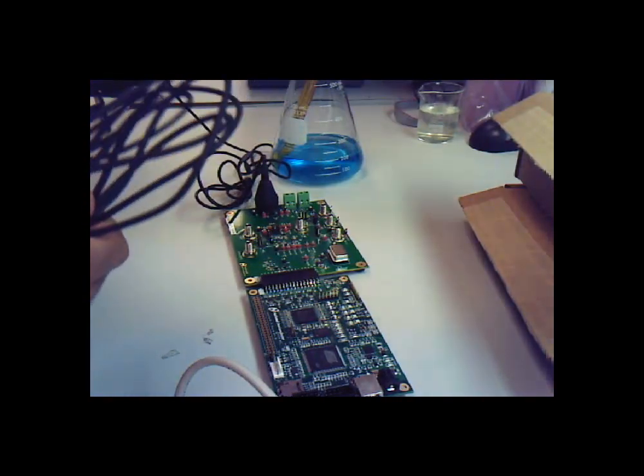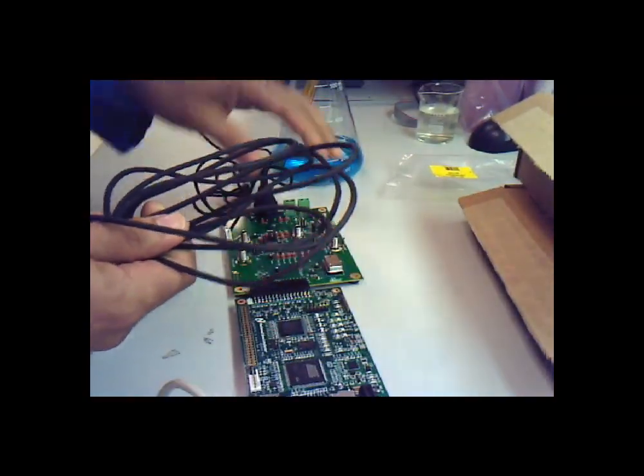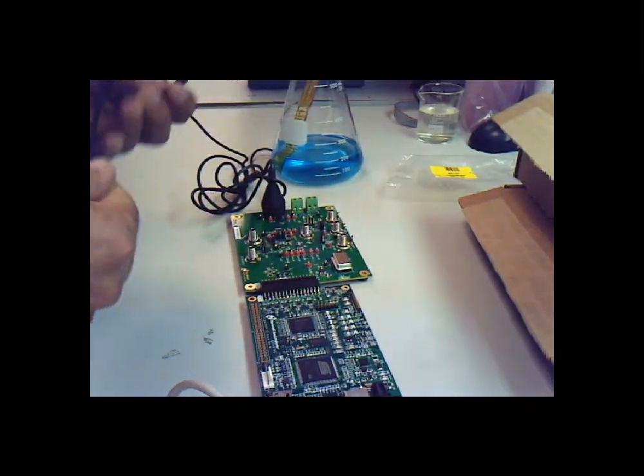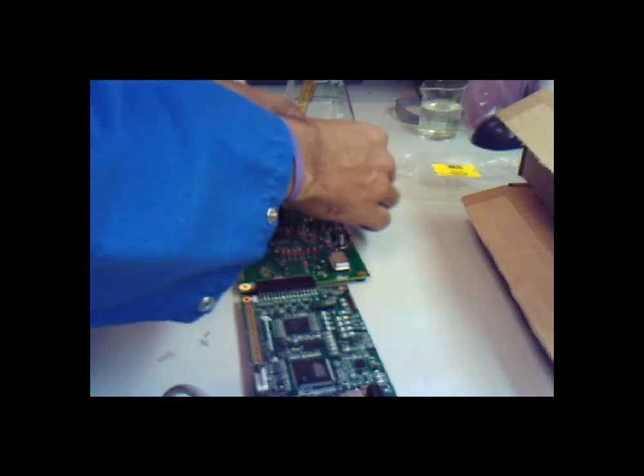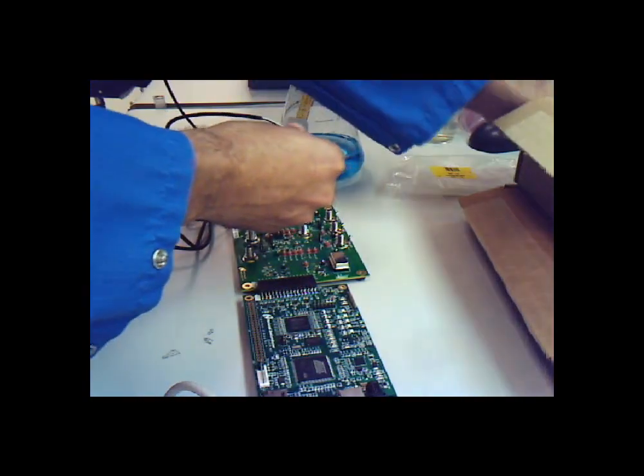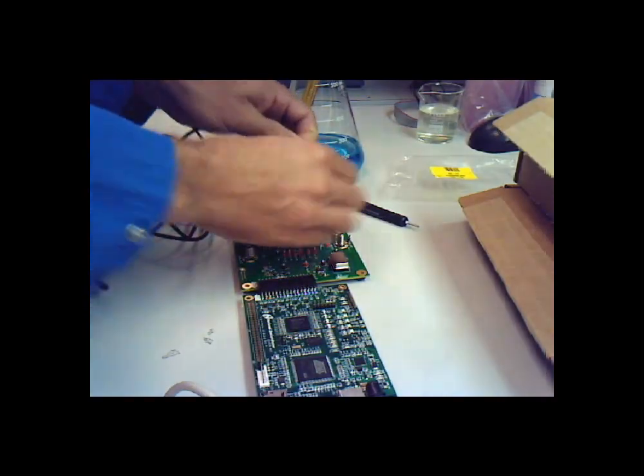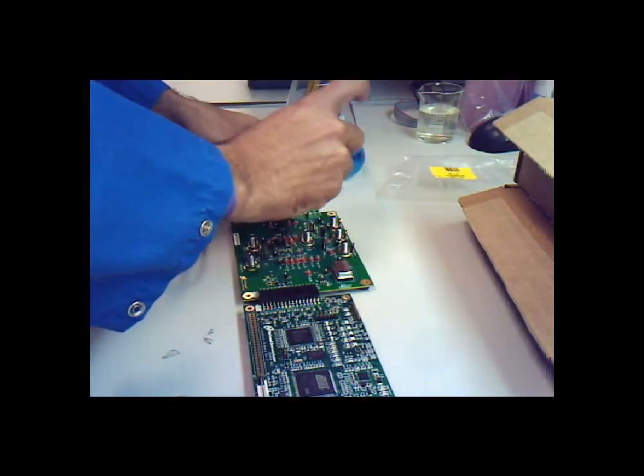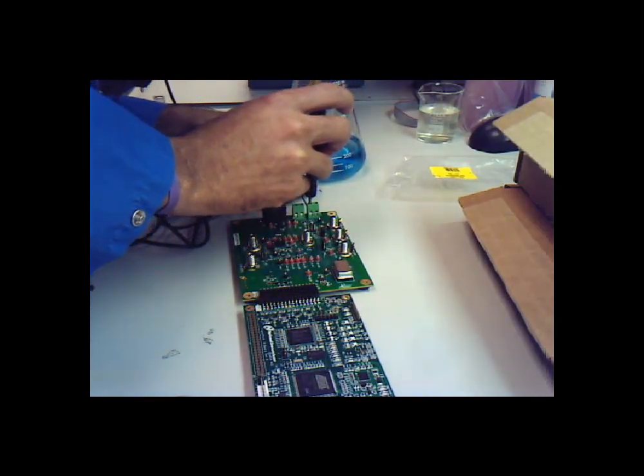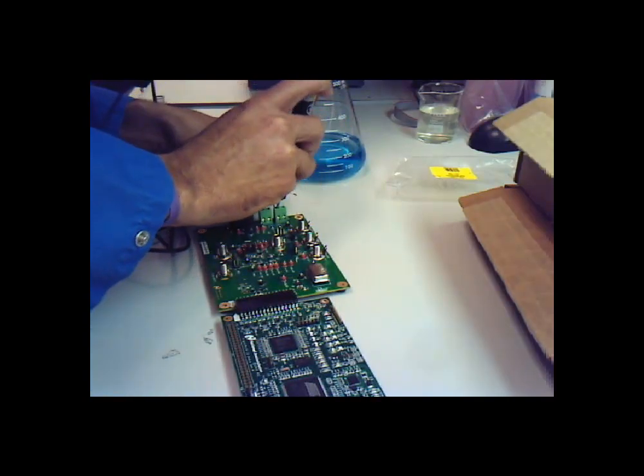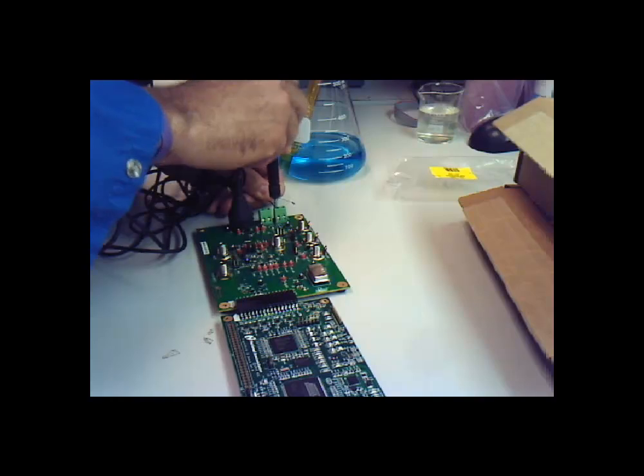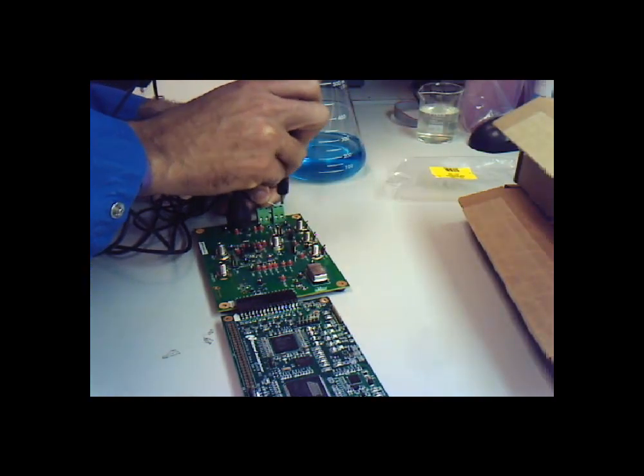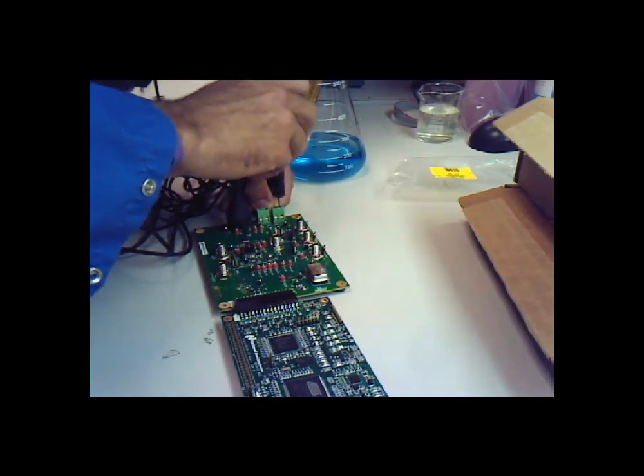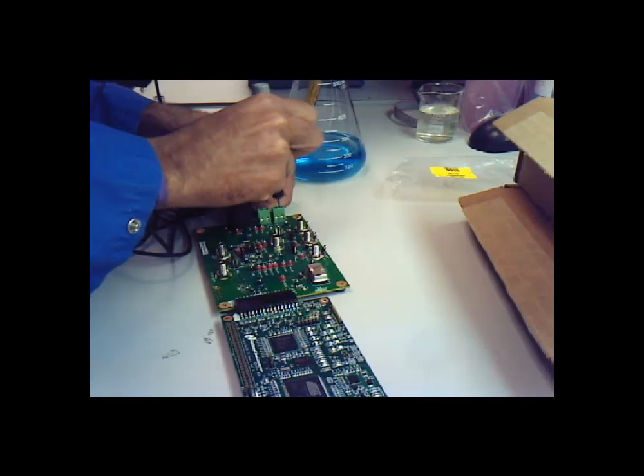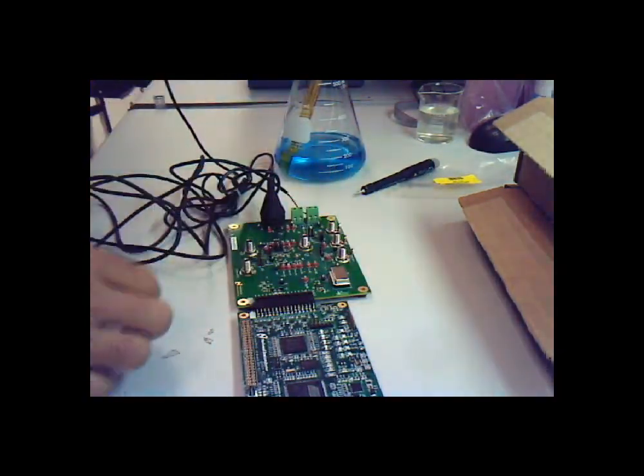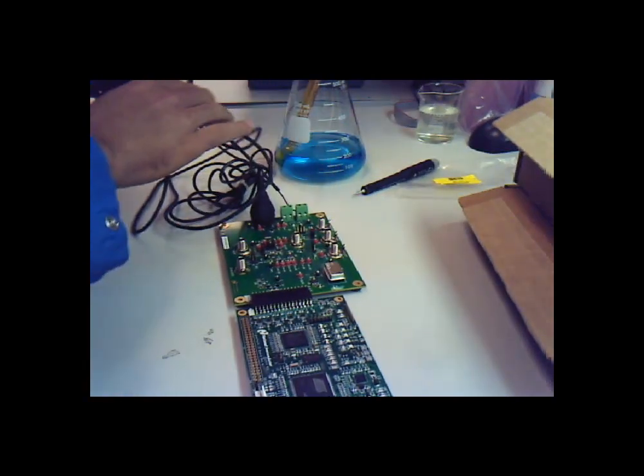Let's connect the RTD. The top left corner of your board, you'll have an RTD input. RTD is just a resistor, so the polarity doesn't matter. Grab a small flathead screwdriver and connect it as such. Make sure it's secure. You can also stick your RTD into the solution.